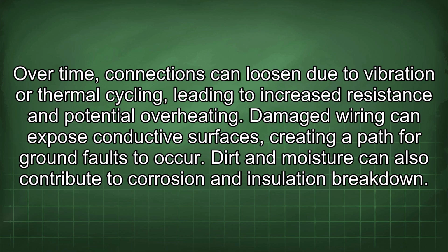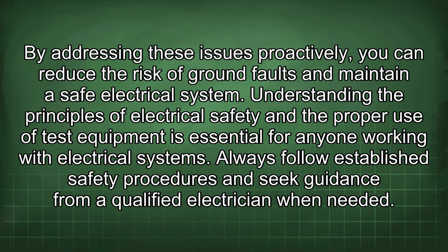Over time, connections can loosen due to vibration or thermal cycling, leading to increased resistance and potential overheating. Damaged wiring can expose conductive surfaces, creating a path for ground faults to occur. Dirt and moisture can also contribute to corrosion and insulation breakdown. By addressing these issues proactively, you can reduce the risk of ground faults and maintain a safe electrical system.